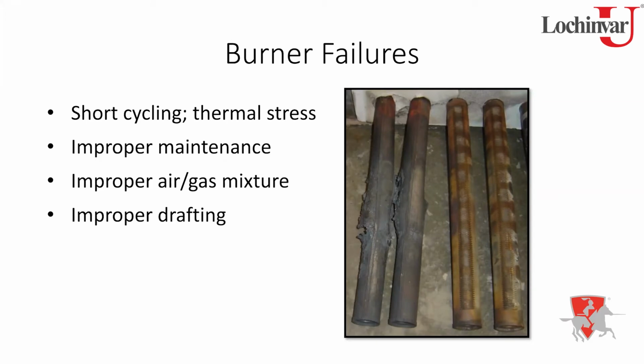So what will then happen is those ports start getting plugged, that flame will start to pull into the burner surface slightly. And as that flame comes into the burner surface, that's when you start to overheat it. And that's what's going to cause the damage. Ideally, the flame should never come in contact with that stainless. It's always going to be setting off the surface. So when you start plugging those ports up, that's when you get that damage, that heat starts pulling back into the burner. That's when you create that issue.